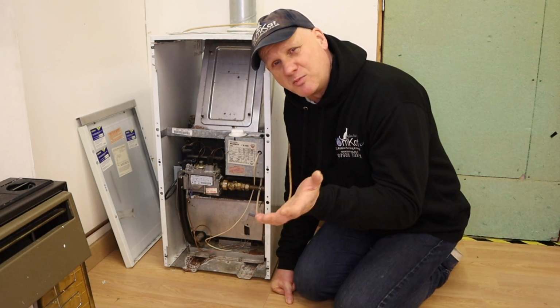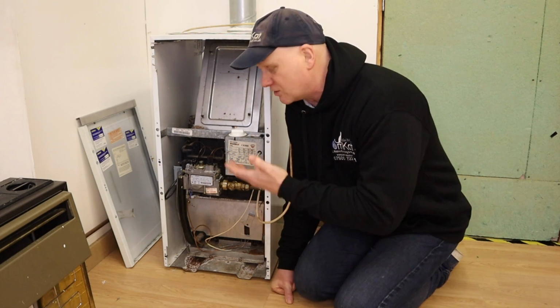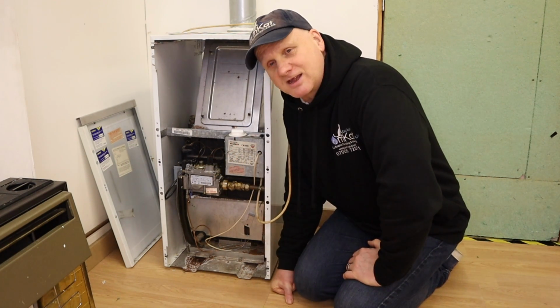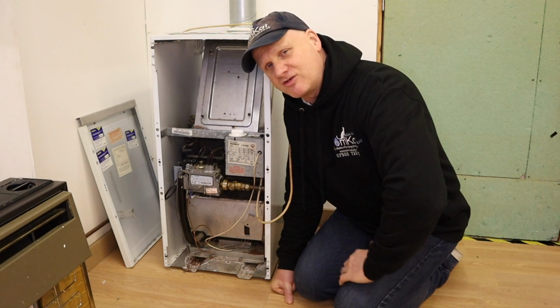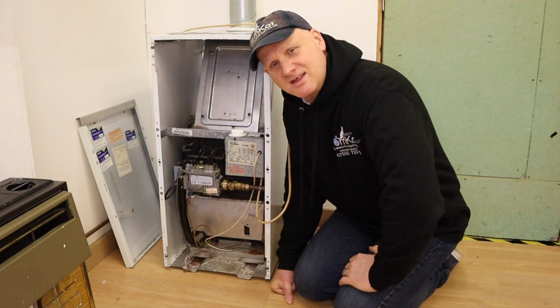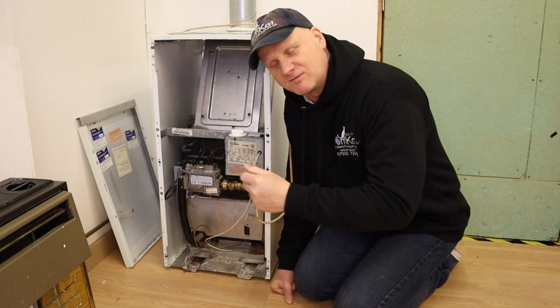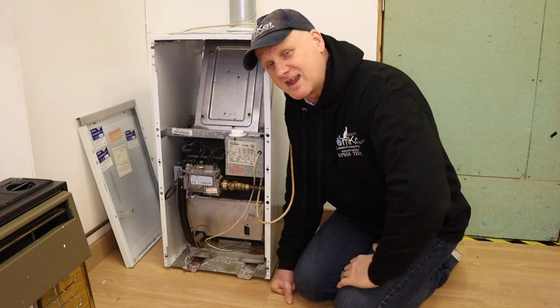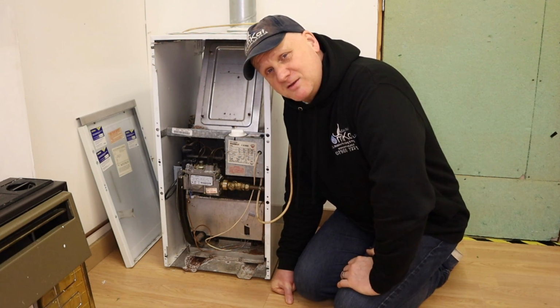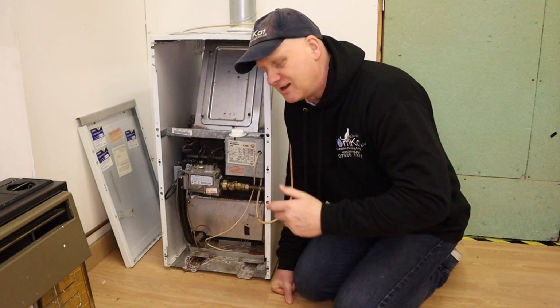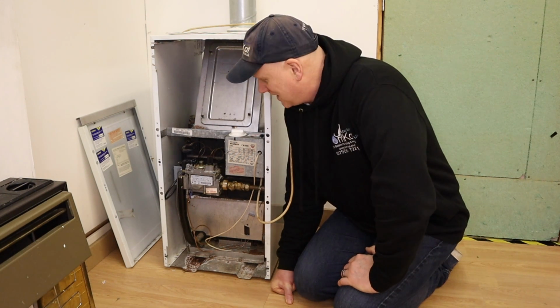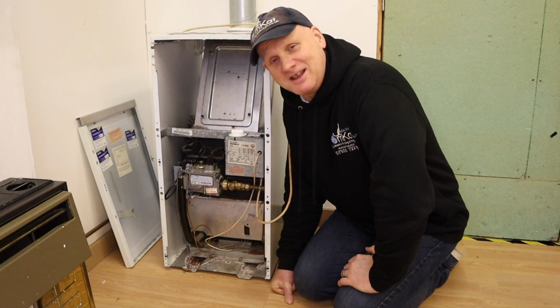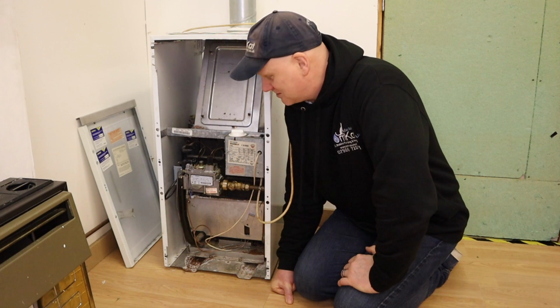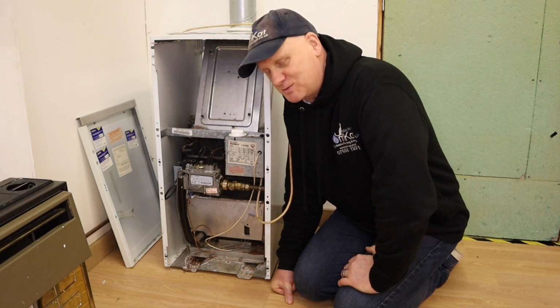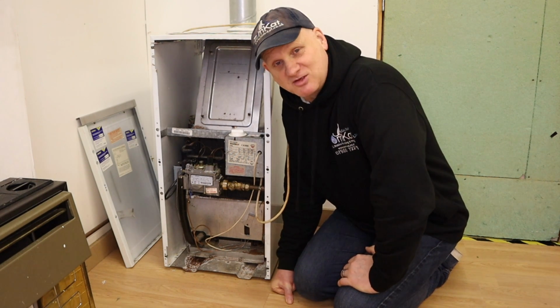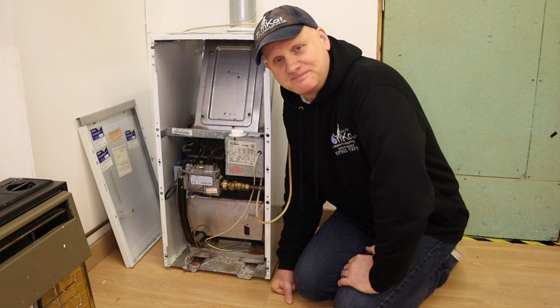So there are some oil boilers out there and some commercial boilers where the heat exchanger is still cast iron, but they have a secondary heat exchanger which takes more heat out of the products of the gas, which then condense. Because stainless steel is impervious to the acidic water, we get away with it that way. So in a nutshell, that's cast iron heat exchangers. Heat exchangers which shouldn't be around today, but for some reason people still love them.